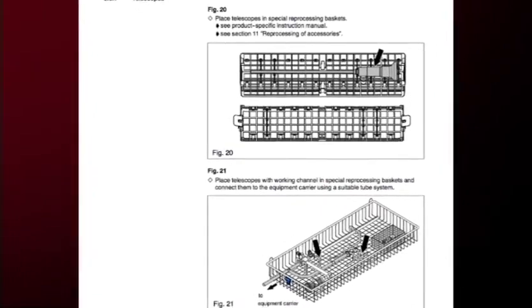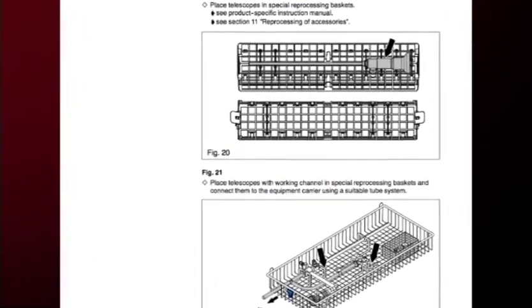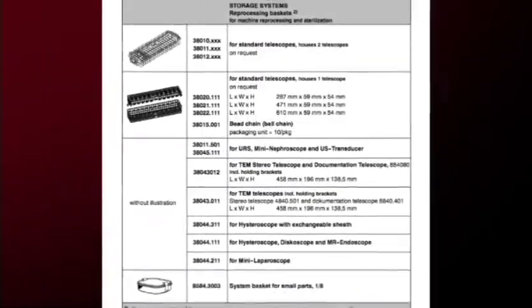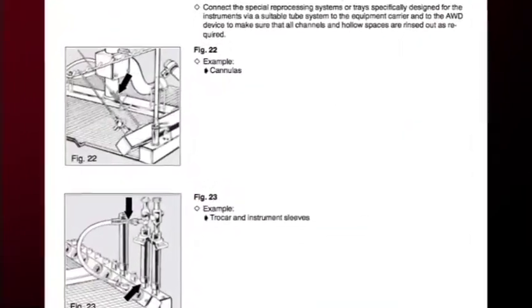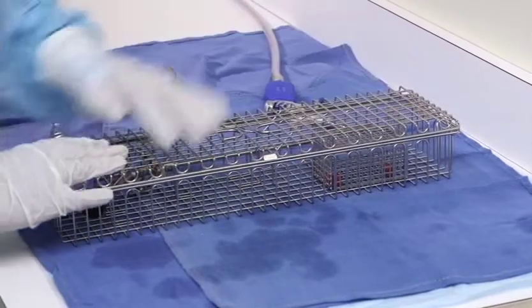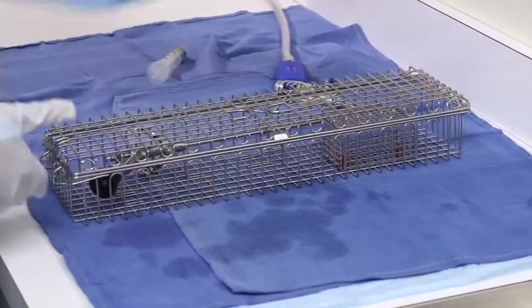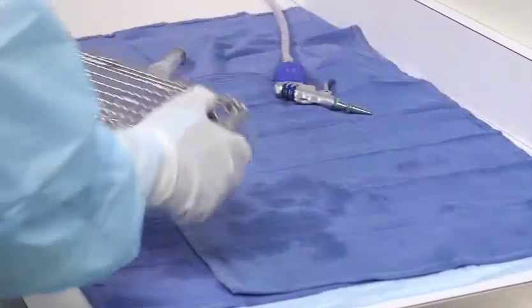Always check the endoscope's manual to ensure the automated washer disinfector has been validated to decontaminate and disinfect the rigid endoscopes and instruments. Use the correct baskets, carriers, and connectors for the endoscopes and instruments to ensure thorough cleaning and prevent damage.